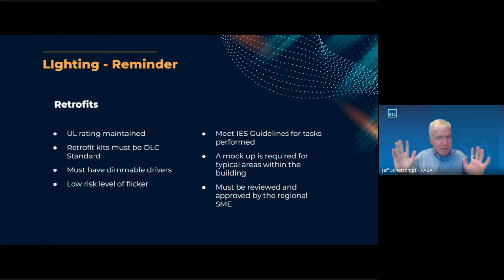Here's one that admittedly a few of us may have missed. A mock-up is required for typical building areas to ensure lighting quality, output, and control are appropriate. This means doing a couple of key areas first, checking them out before you move on to the next spaces or moving further down the hallway, whatever the case may be. You want to do that test scenario first. Make sure it's what you think it's going to be.